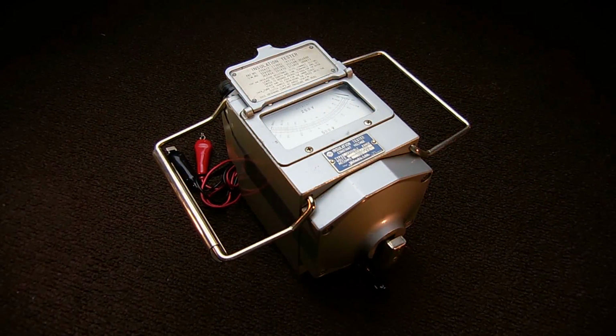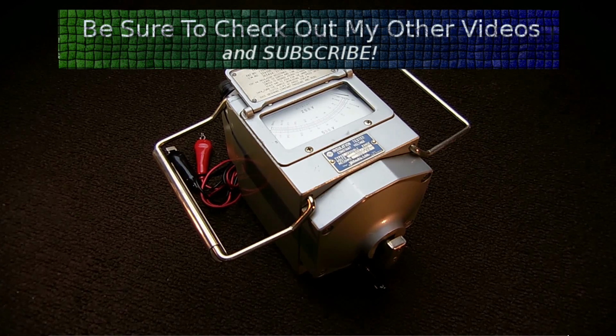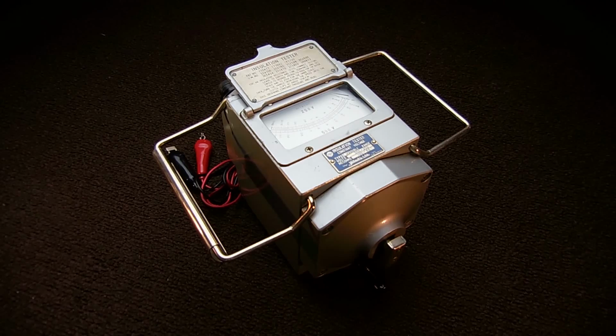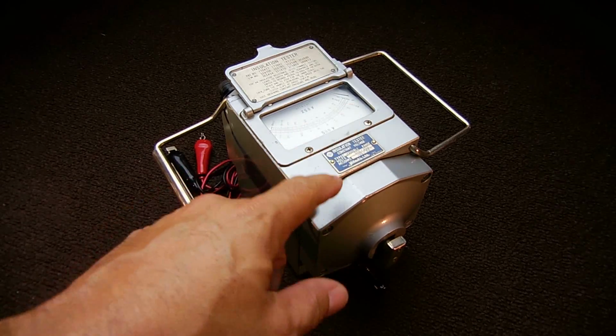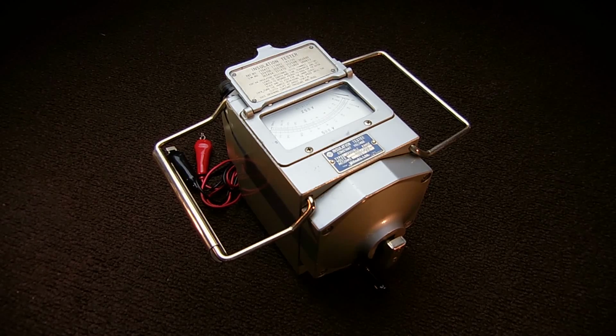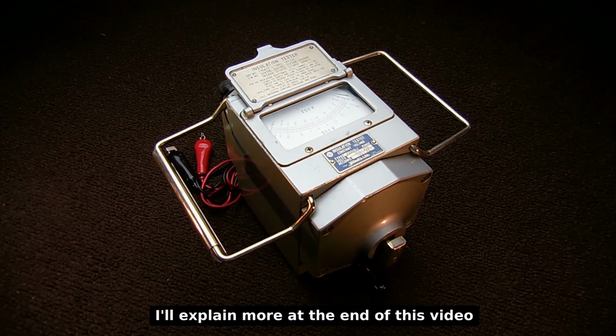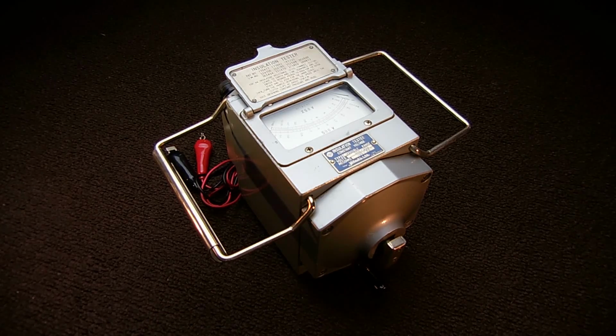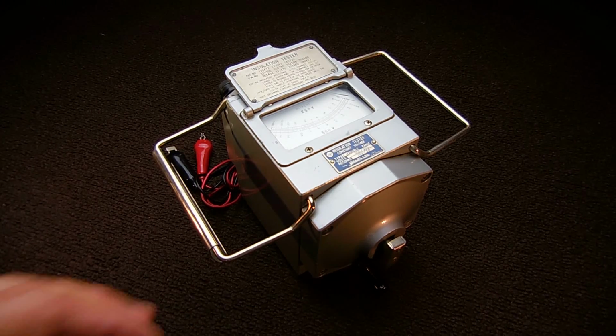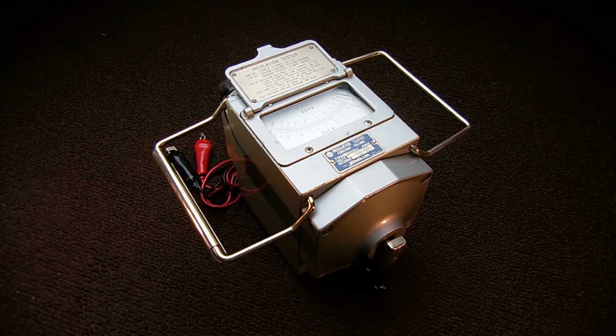Insulation testers are extremely useful, and as I said earlier, you can check motor windings, transformer windings, and if you're an electrician, if you're going to be pulling lines through a metal conduit, you may want to make sure that it's completely isolated from other wires within that conduit. You may also have a problem that in your electrical panel, one of the breakers keeps tripping, and it does not do it all the time. It could be an intermittent short circuit, and these are excellent for finding out which wire in that conduit is the problem. Anytime you have an intermittent problem, where breakers trip on and off sometimes, you're definitely going to want to inspect the circuit or the motor connected to that circuit using a Megger.